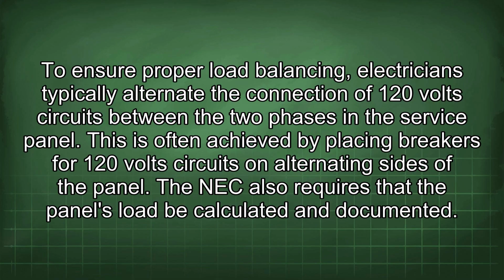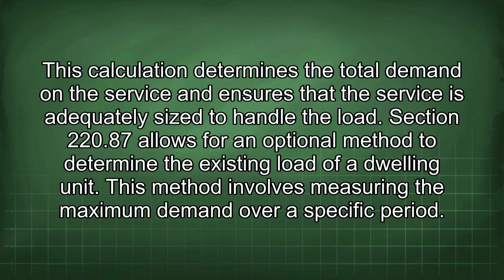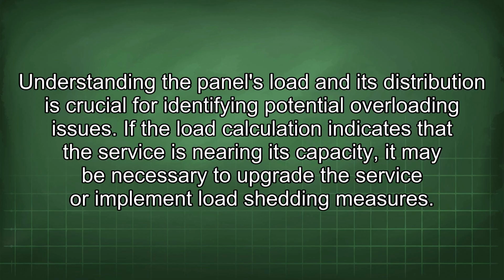The NEC also requires that the panel's load be calculated and documented. This calculation determines the total demand on the service and ensures that the service is adequately sized to handle the load. Section 220.87 allows for an optional method to determine the existing load of a dwelling unit. This method involves measuring the maximum demand over a specific period. Understanding the panel's load and its distribution is crucial for identifying potential overloading issues.